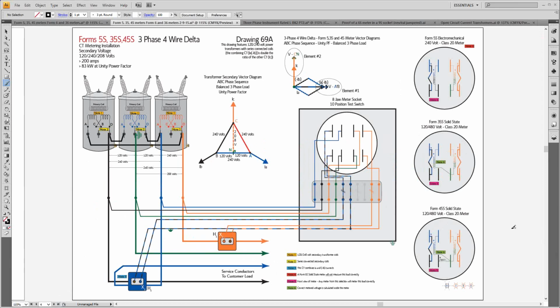But as we look at this and see the 4-wire delta, what happens in this one is that we have 3 energized phases and then the neutral, which makes up the 4th wire in our system. And so, according to Blondel's, if I have 4 wires, like 4-wire delta shows here, I should have 3 meter elements. Again, we're going to trick Blondel's, take it clear down to 2 meter elements, save the cost of a CT, save the cost of a potential coil and an element in our meter. And again, this is how we did most of our 4-wire deltas, just like this.